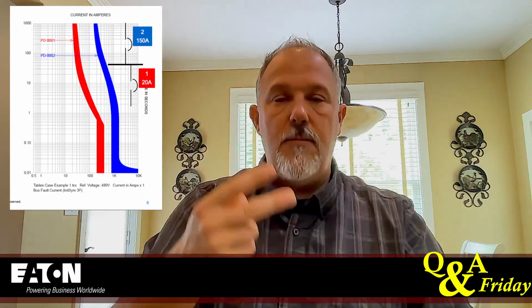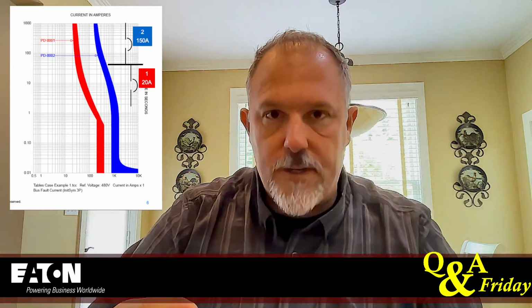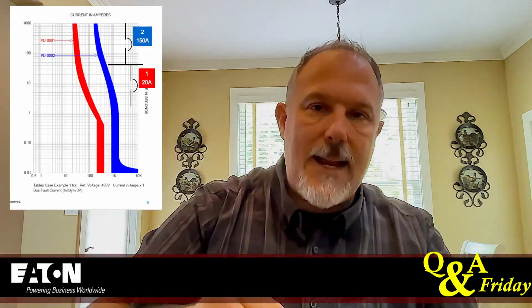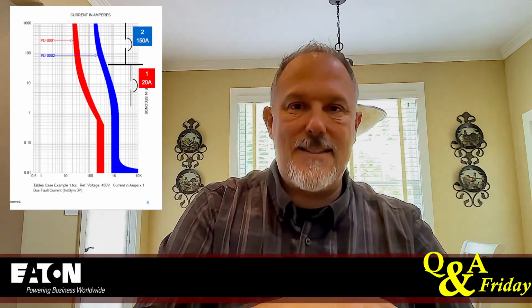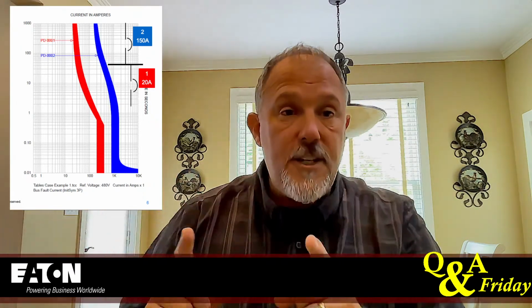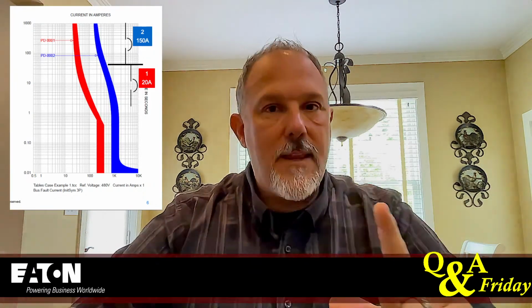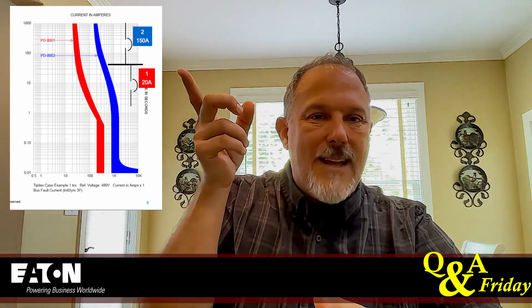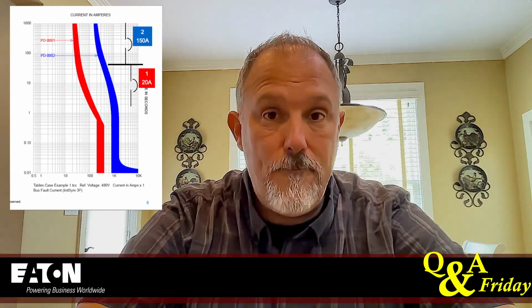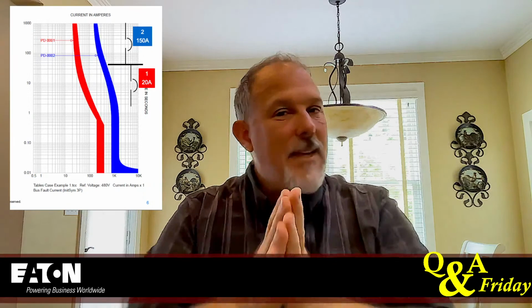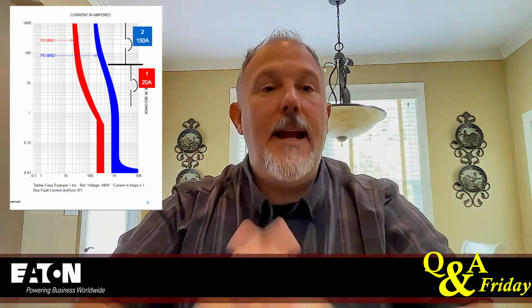2,000 amps. If you get your available fault current less than 2,000 amps, IEEE 1584 tells us the likelihood of that arc sustaining itself is less. And I would almost argue it's not going to sustain itself. The amount of energy is too low. So if I can knock it down below 2,000 amps of bolted fault current value, I meet my selective coordination for these two breakers. I've added a transformer though. So that's another problem. And what that does is that makes me put another breaker as a main instead of a main lug only panel. And then you get to the coordination through a transformer, which is another video that I did. Stuff. Love it.